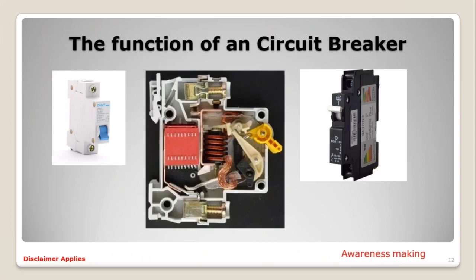And the same with a circuit breaker. A circuit breaker can't function or see an inrush of current if there's no earth connected to it. Let's say there's a dead short, or a live to neutral contact, or a live to earth contact, the circuit breaker will have the same function in tripping. That's why it's important to have your system, the geyser or the component, earthed so that this circuit breaker can see the fault current wherever it touches the live part.